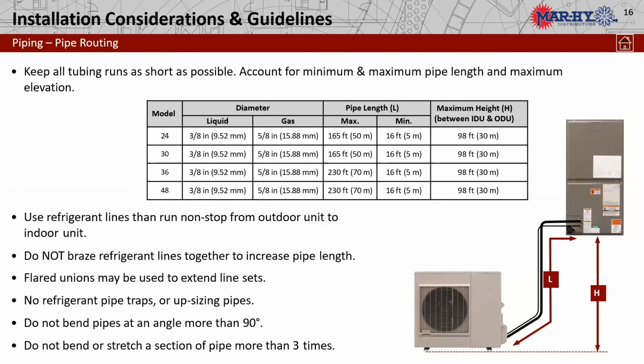That's going to be what, there's no fudge factor, because I don't know what's going to happen. The maximum vertical separation on all units is basically 100 feet, 98 feet, which is great. That's a long ways. So as we look at our 36 and 48, 3 and 4 tons, the same line set, 3/8, 5/8, we can do a max of 230 feet. That's a long ways. With a 16-foot minimum and a 98-foot vertical separation. All good news there.